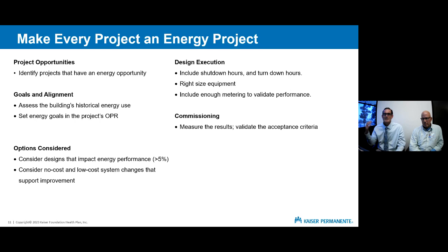Also during design, we need to set the goals for commissioning. There's a bunch of things we need to execute correctly: shutdown hours, turn down hours, equipment sizing, and including enough metering to validate performance. That becomes really important when we move into commissioning.